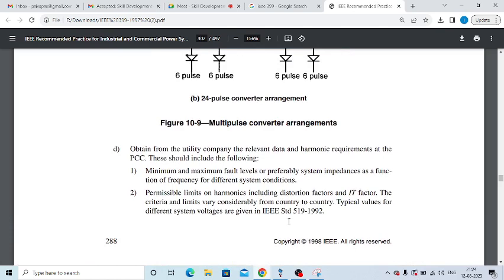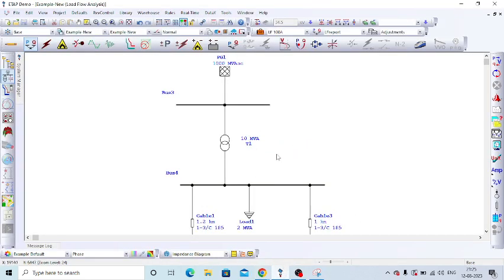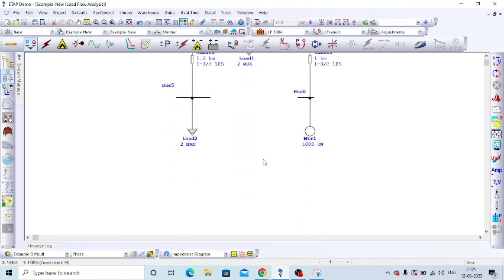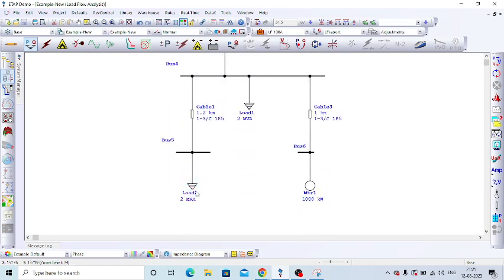Okay, then the next one is to obtain relevant utility harmonic data. We see a single line diagram like this. Here the grid is the power source. Utility means the grid only. The grid also has some harmonic voltage. So we have to get the grid capacity, that is the harmonic voltage, technically called the background harmonic voltage. We have to get that background harmonic voltage, and also its short circuit strength. Suppose this particular load is a harmonic producing load, then for this load we have to get the harmonic current generation data.